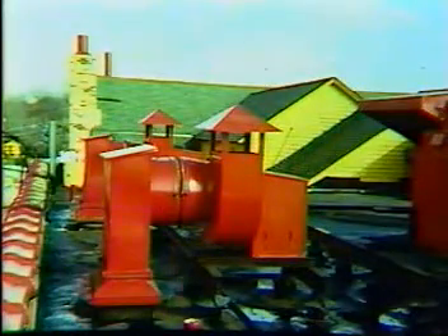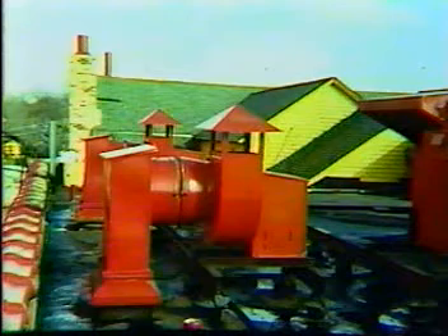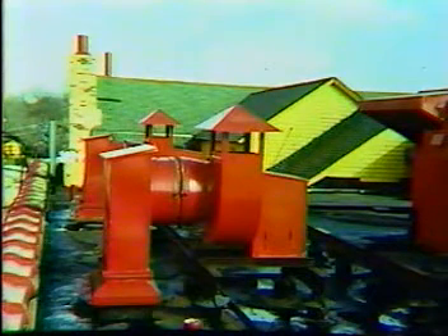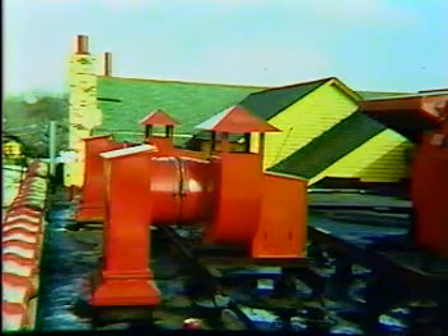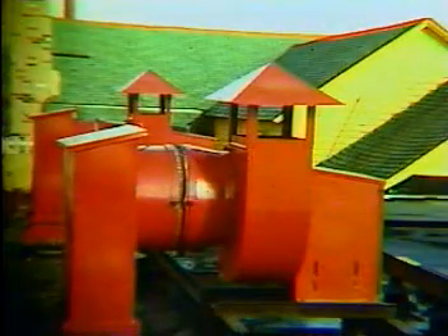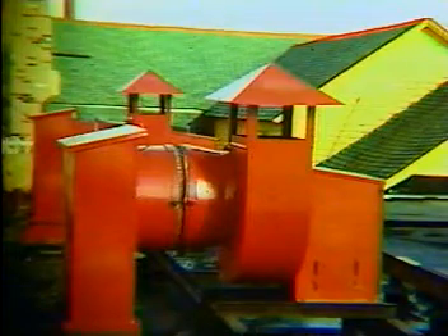Example: two fans with 15-inch diameter wheels located on top of a restaurant are used to exhaust kitchen smoke and fumes. These fans are required to move 6,000 cubic feet of air per minute, or CFM, 16 hours a day.